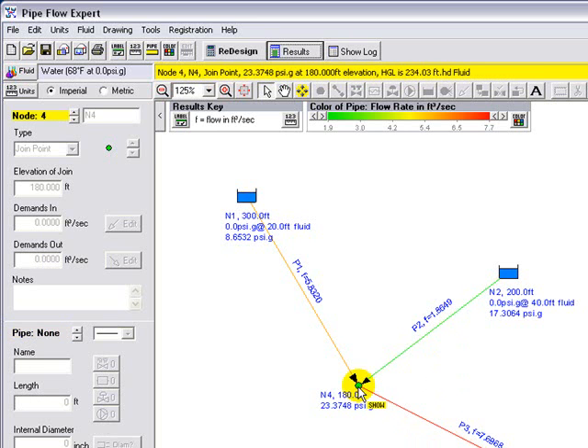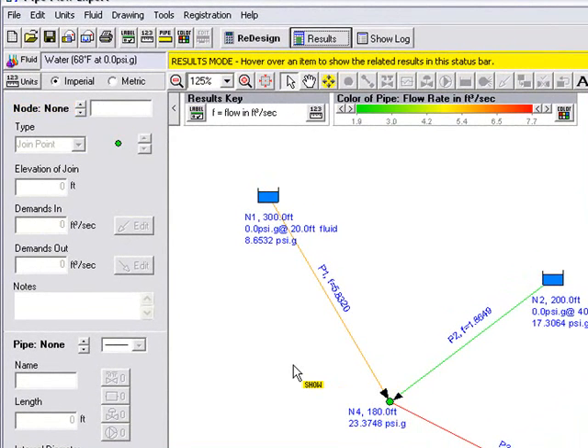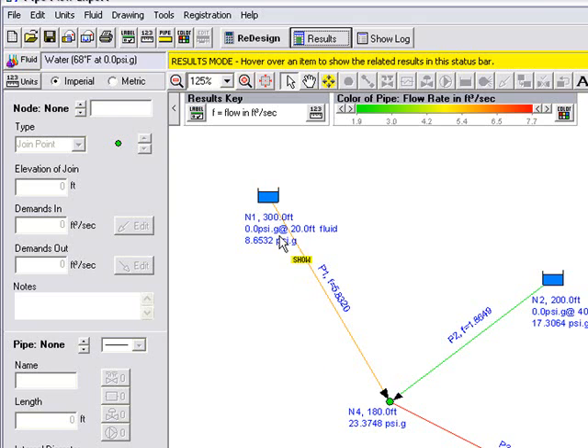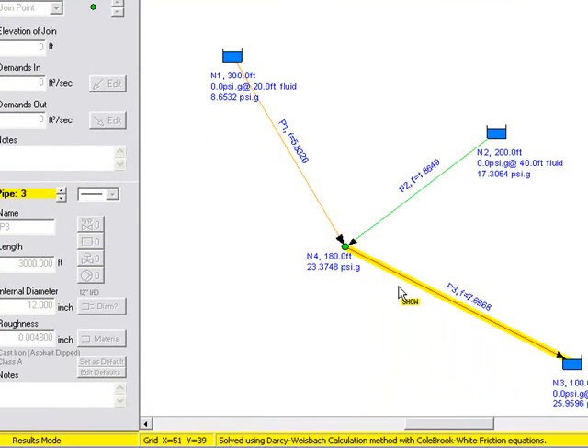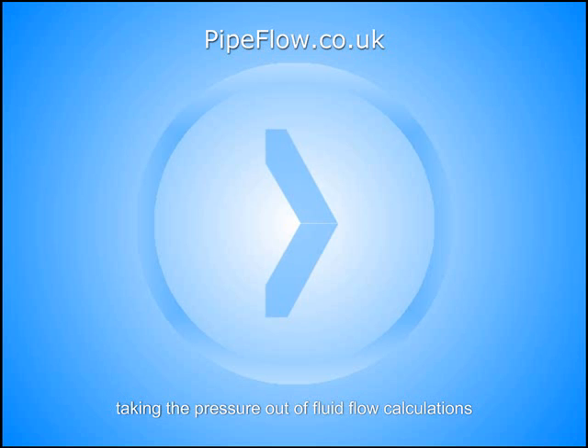If we hover over a node we can see the pressure at this point in the system which is shown as 23.37 psi gauge and as we know we set that elevation of that point to be 180 feet where the pipes came together. So this gives a good demonstration of quickly being able to draw a visual representation of your system and being able to solve that system. And in this case we have solved a classic 3 reservoir problem to solve the flows under gravity from two reservoirs to a common point and then joining to a single pipe down to a third reservoir.